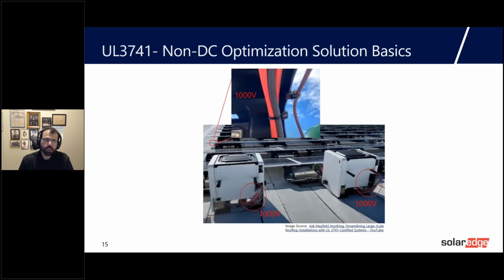Okay. Now let's look at the other solutions, what we call the non-DC optimizer solutions. 3741 opened the door to allow solutions that use few, if any, MLPE devices to be code compliant. In these solutions, AC conductors are de-energized using traditional string inverters. However, the DC array itself is kept at high voltage levels, 1,000 volts, even after a rapid shutdown is initiated, corresponding to hazard level 3.